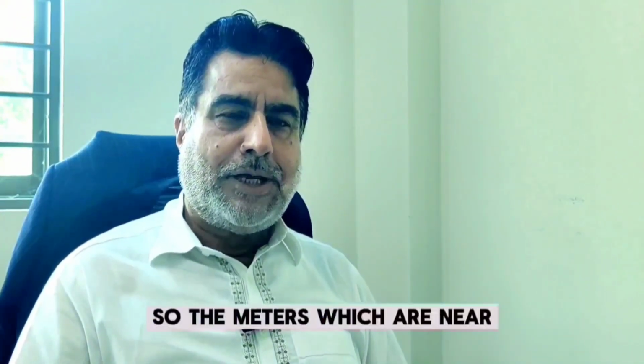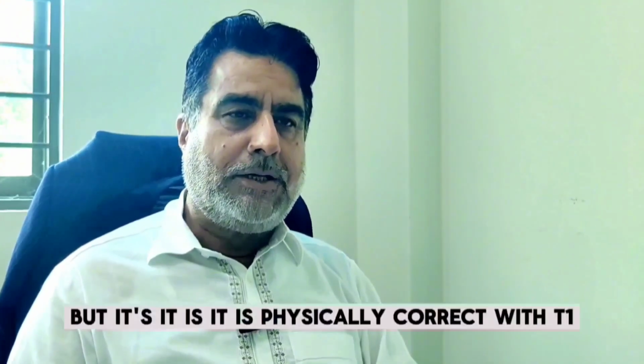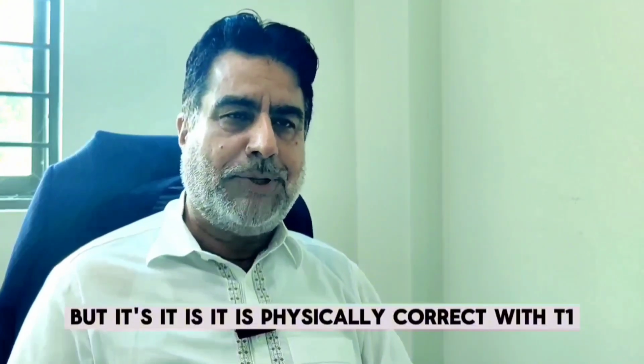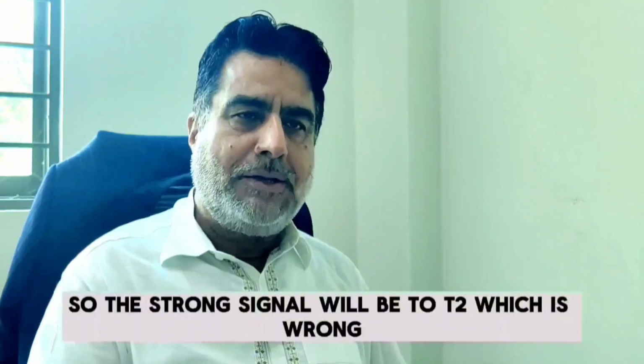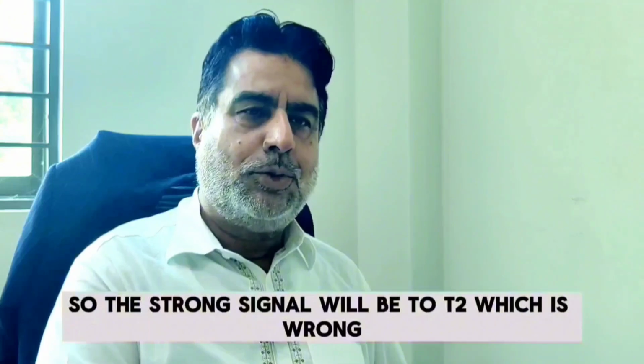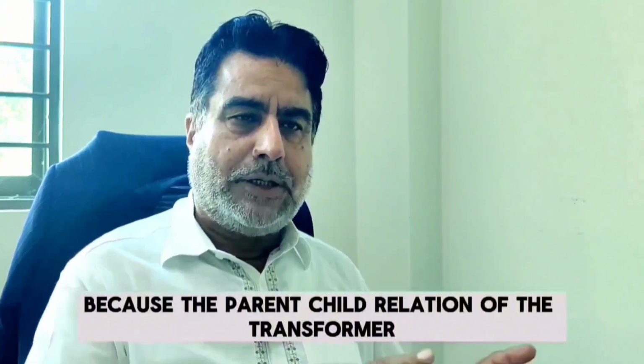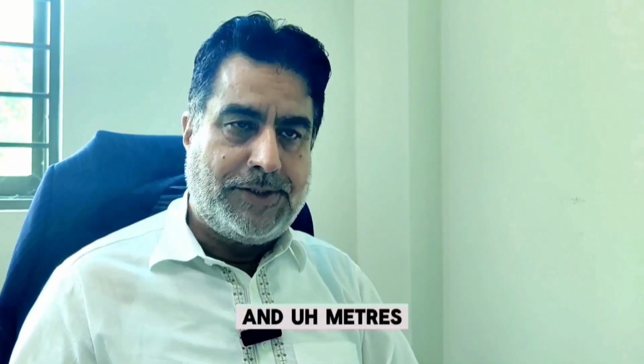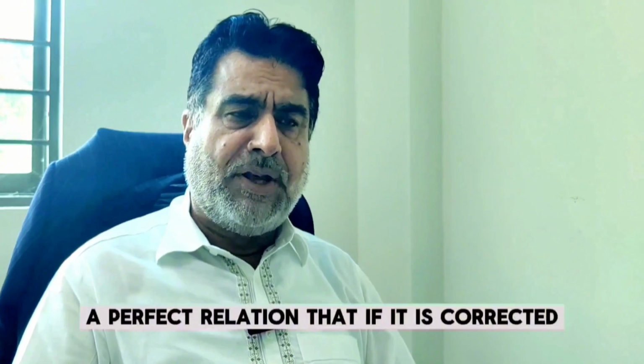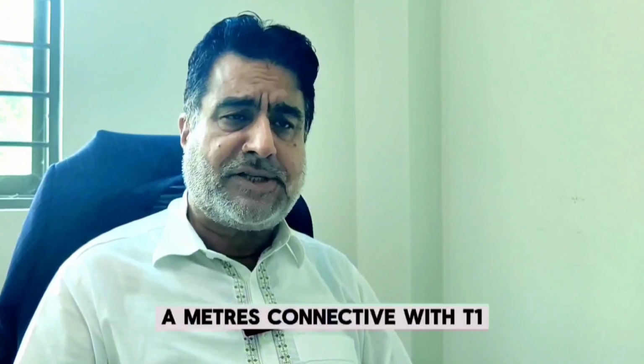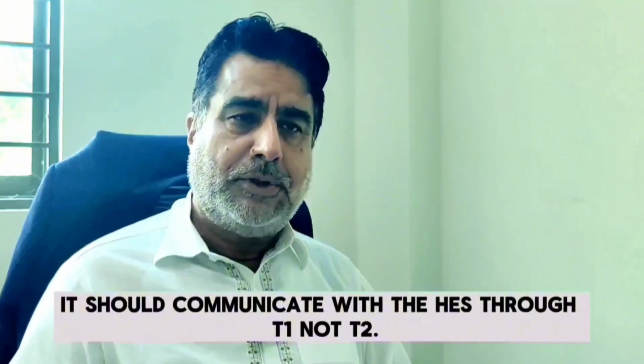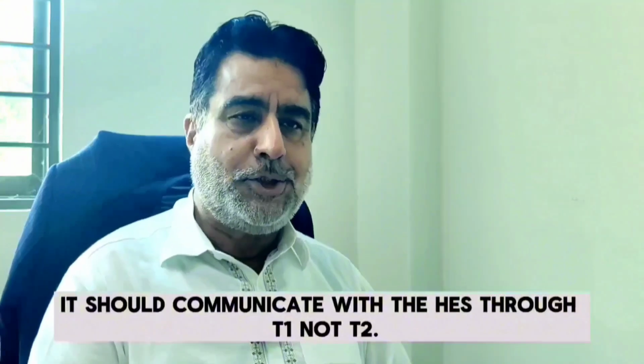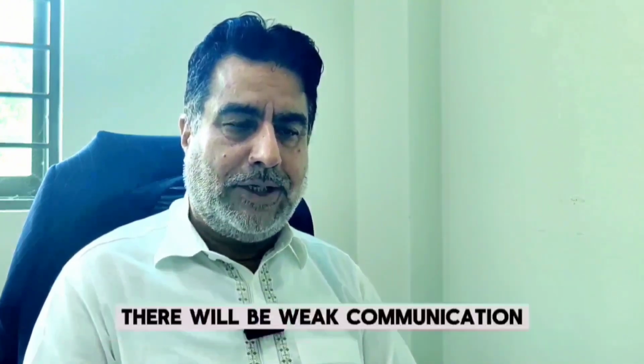So take a meter which is physically connected with transformer T1 but is near to T2. The strong signal will be through T2, which is wrong. Why is it wrong? Because the parent-child relation of the transformer and meters is a perfect relation: if a meter is connected with T1, it should communicate with the HES through T1, not with T2. So if the neutral is common, communication will be scattered, and there will be weak communication.